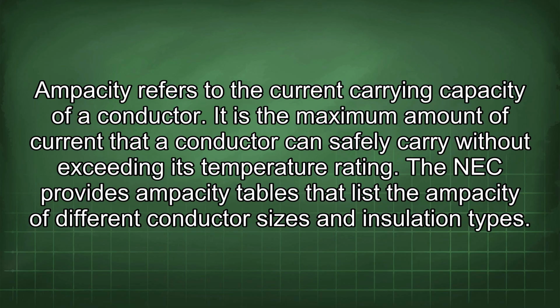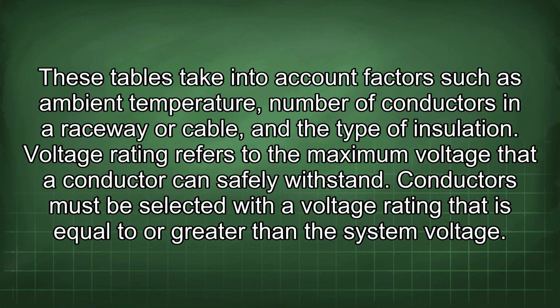Ampacity refers to the current carrying capacity of a conductor. It is the maximum amount of current that a conductor can safely carry without exceeding its temperature rating. The NEC provides ampacity tables that list the ampacity of different conductor sizes and insulation types. These tables take into account factors such as ambient temperature, number of conductors in a raceway or cable, and the type of insulation.